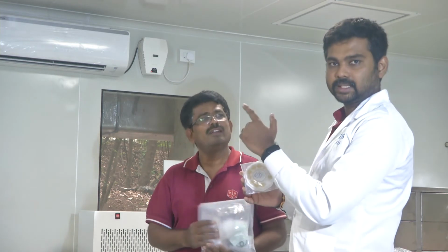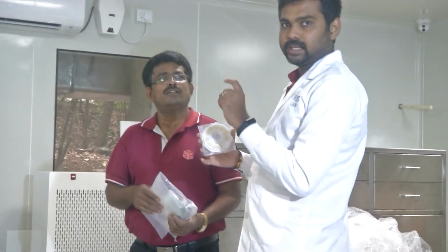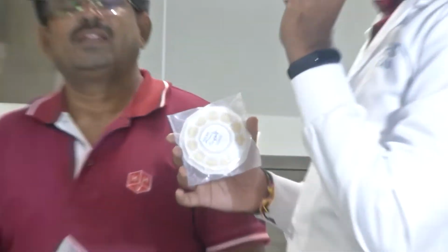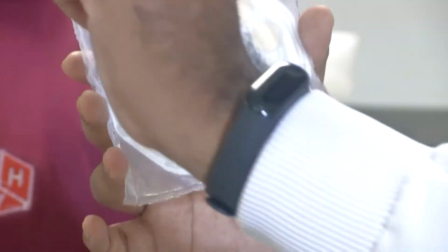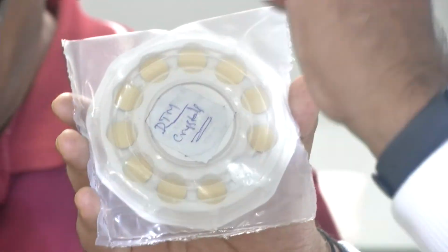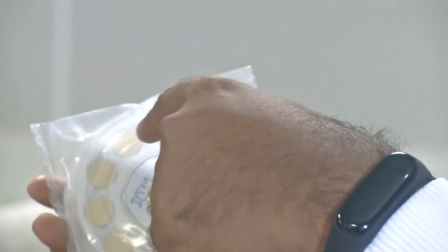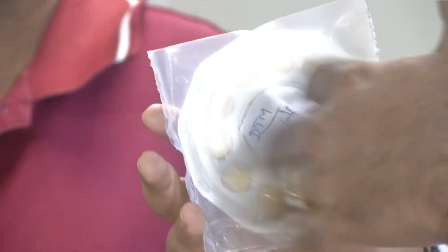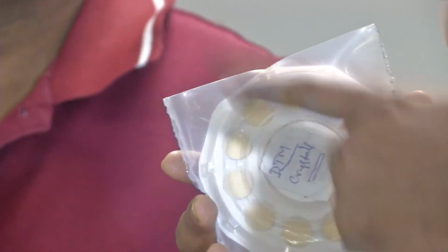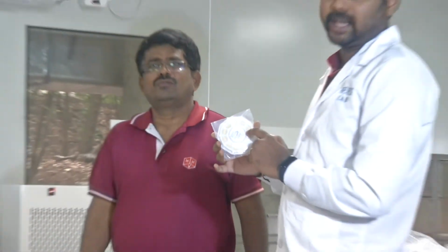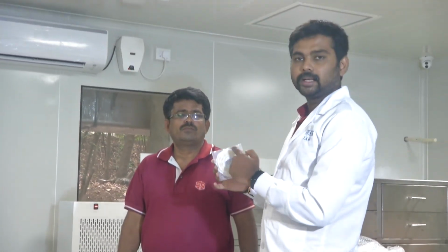These are crystals. As we have seen inside, there is a quartz crystal monitor inside. That is very critical because it measures the deposition rate and the thickness that is deposited. The crystal also gets deposited in the process, so we have to change the crystal quite often. Otherwise, our calibration of the thickness measurement will get affected. So they have given spares. 10 crystals are there, which we can replace.